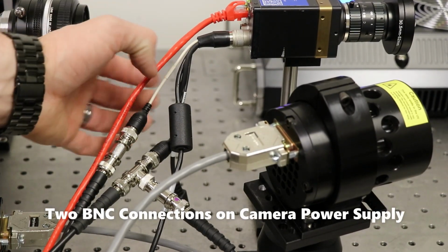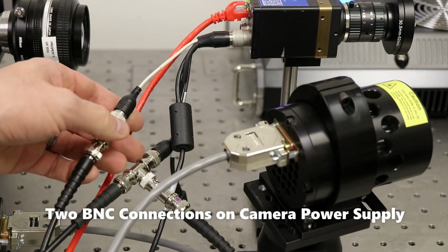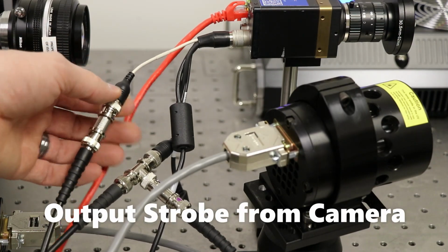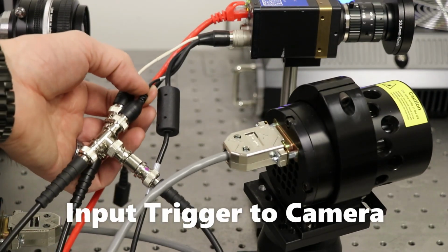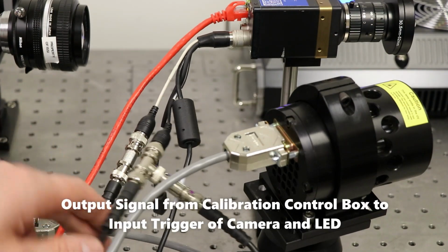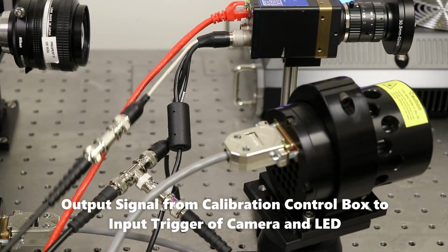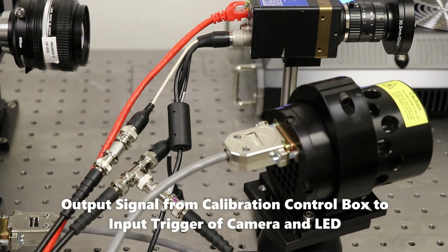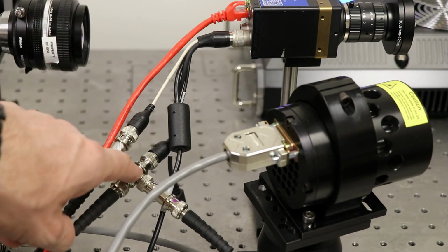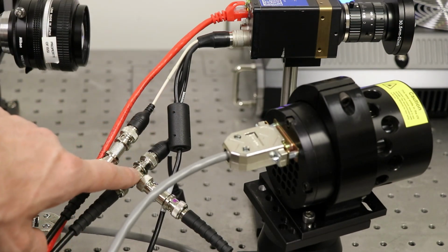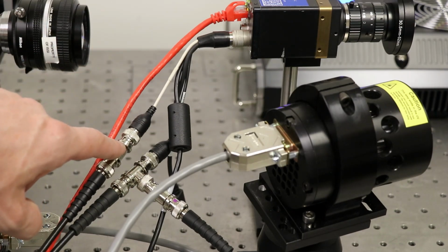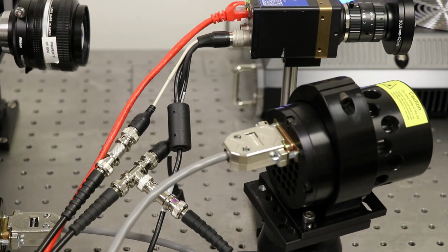On the camera power supply, there are two BNC connections. One is for an output strobe, the other is for input trigger. So as we discussed earlier, we have one line coming from the calibration system box that will trigger the camera and the LED to take an image and pulse when it's on condition. The other one will send a trigger back to the calibration box to let it know that it has acquired the image at that condition so it can move on to the next condition.